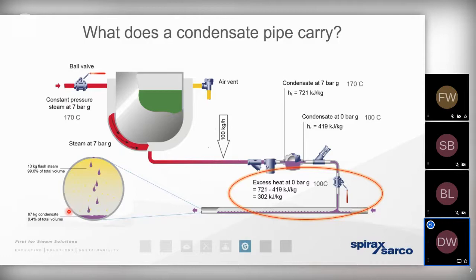So whenever we're talking about increasing or maximizing the amount of condensate we can bring back to the boiler house, we need to talk about the flash steam. We need to talk about either reducing the amount of flash steam that is going to be produced, or we need to look at reusing or recovering that flash steam to use that energy in some other way. There's just as much flash energy in a unit of flash steam as there is in a unit of plant steam. And also, if that flash steam is vented away to atmosphere, well, the problem is that we're missing the opportunity to recover that liquid condensate. The flash steam and therefore the condensate goes into the atmosphere.